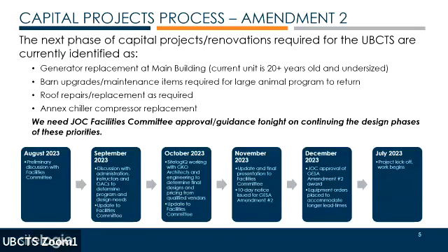Anything is possible, but I would not recommend dual generators. Typically you see dual generators in redundant situations, or where one runs only the life safety equipment and the other doesn't. It just becomes more overhead and costly, and you'd still have the issue of a 21-year-old generator.